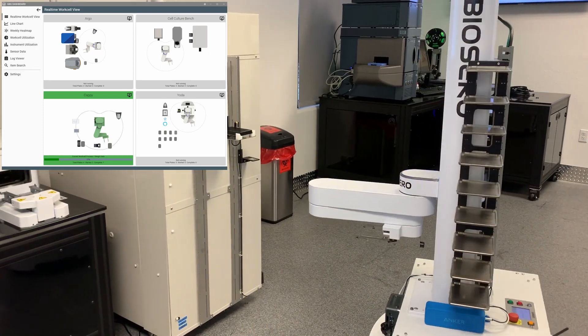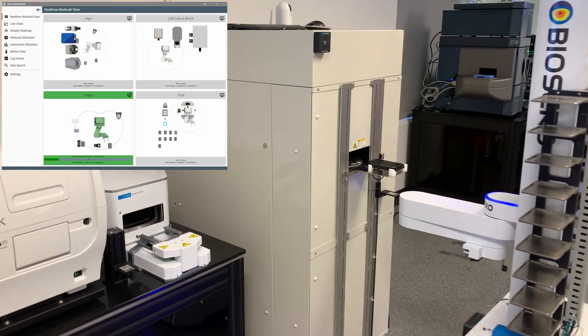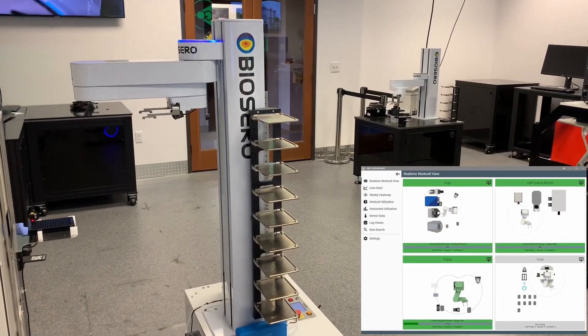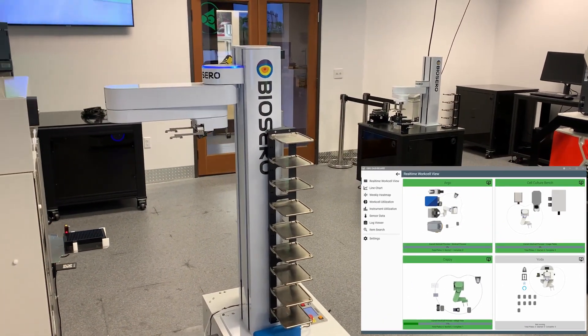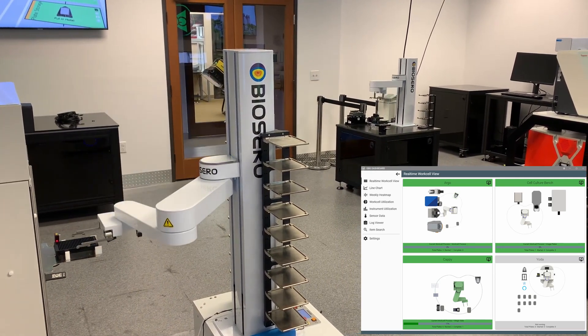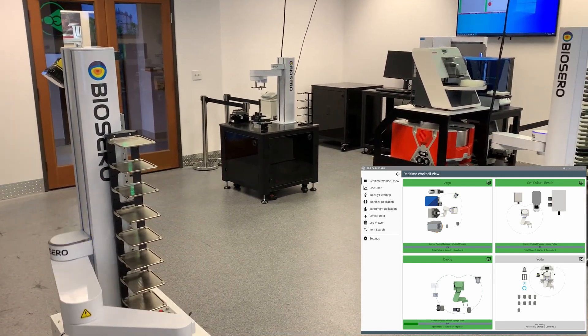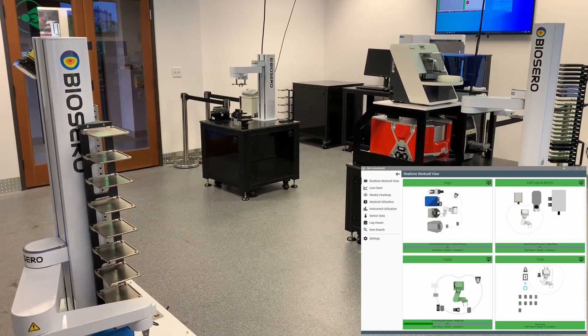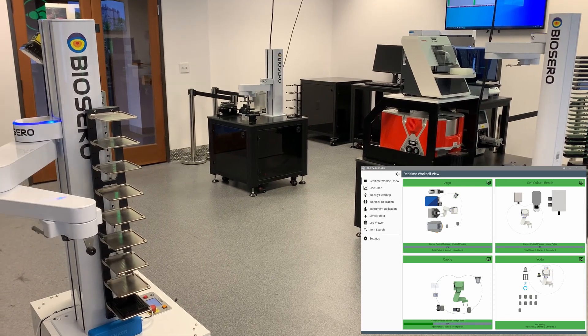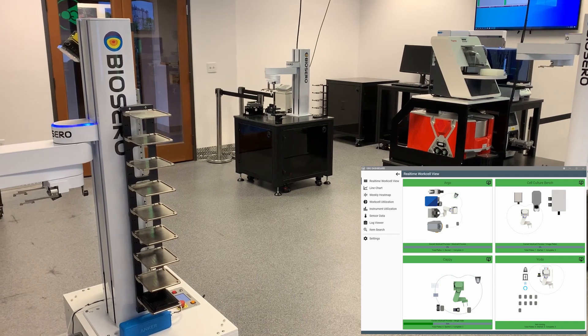The fully automated work cells — Argo, Cappy, and Yoda — the semi-automated cell culture work cell, and the tablet-based manual workstations are individually managed by BioSero's automation scheduling software, known as GreenButtonGo. The room lights, doors, and sensors are integrated and driven by an IoT version of GreenButtonGo. In all, there are about 12 different instances of GBG in the lab. GreenButtonGo methods specific to each of those systems are built and reside on their local computers or tablets.